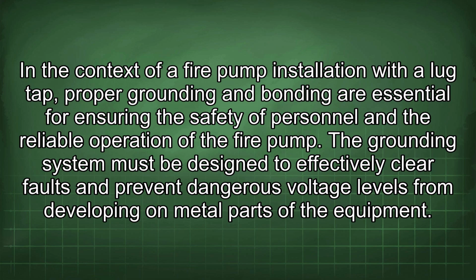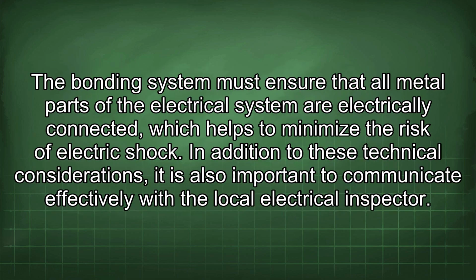The grounding system must be designed to effectively clear faults and prevent dangerous voltage levels from developing on metal parts of the equipment. The bonding system must ensure that all metal parts of the electrical system are electrically connected, which helps to minimize the risk of electric shock.